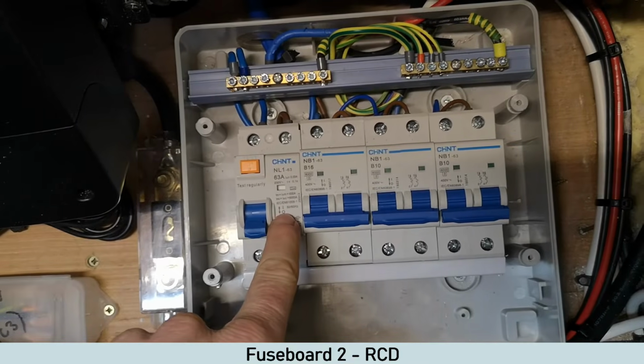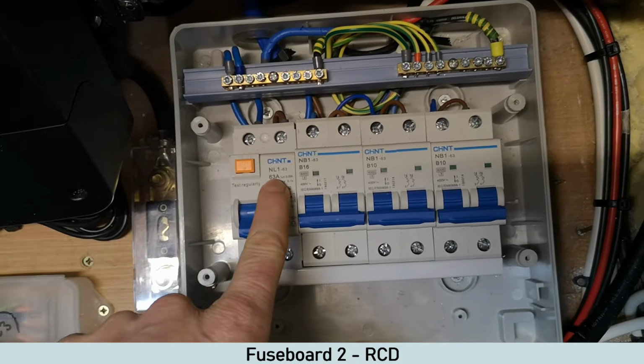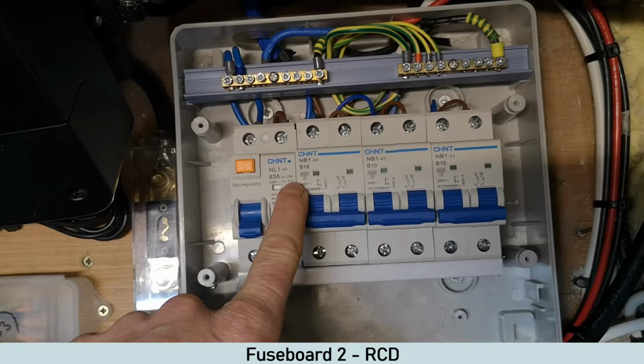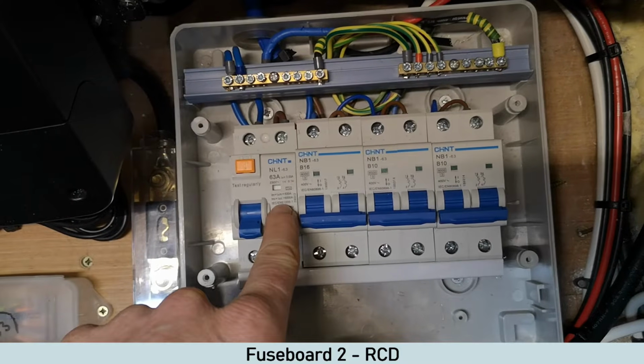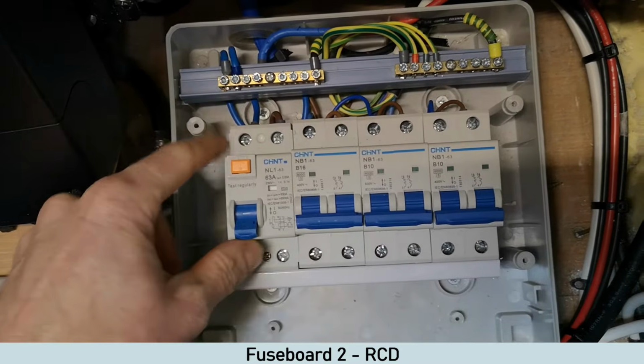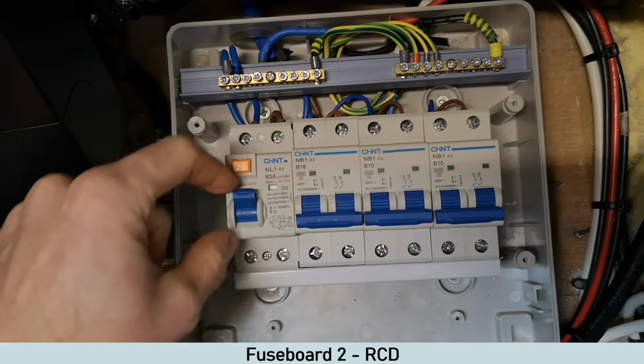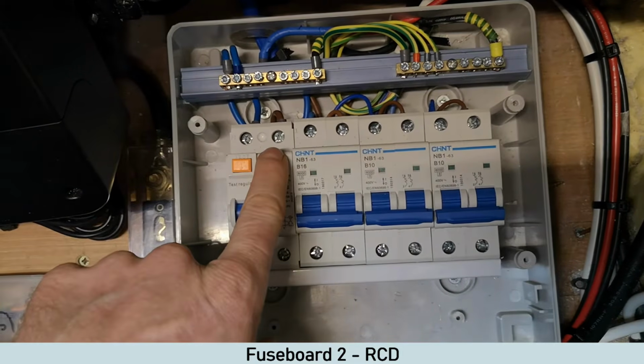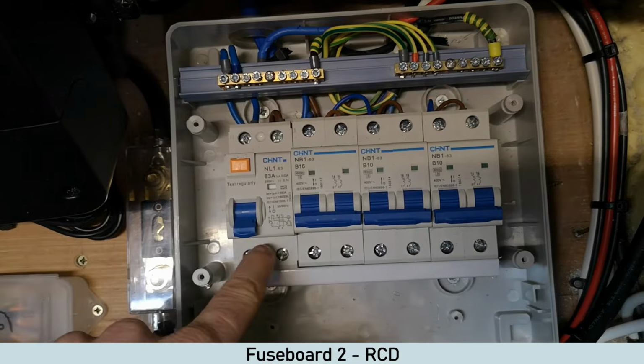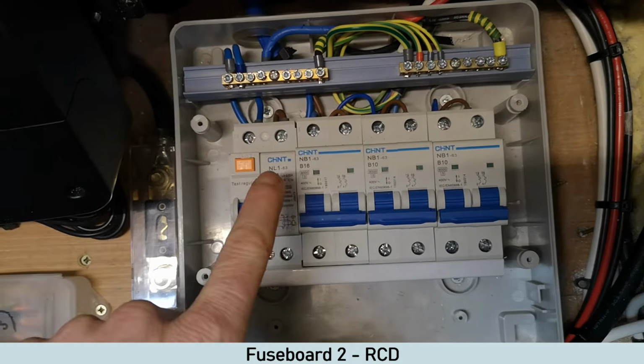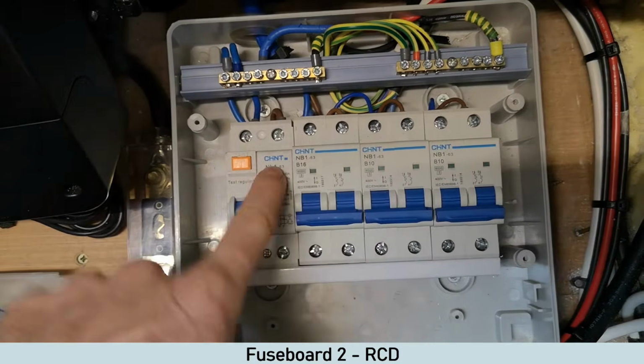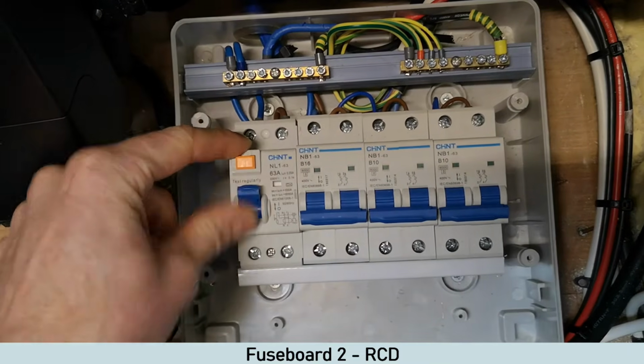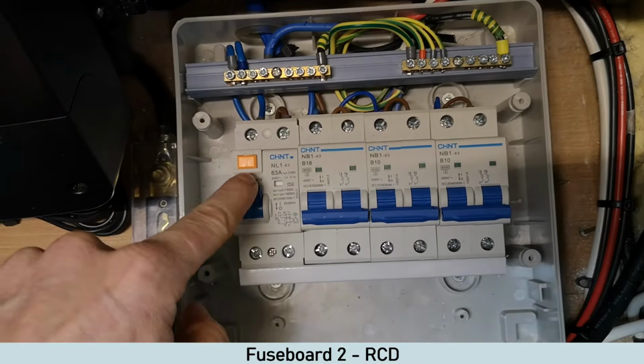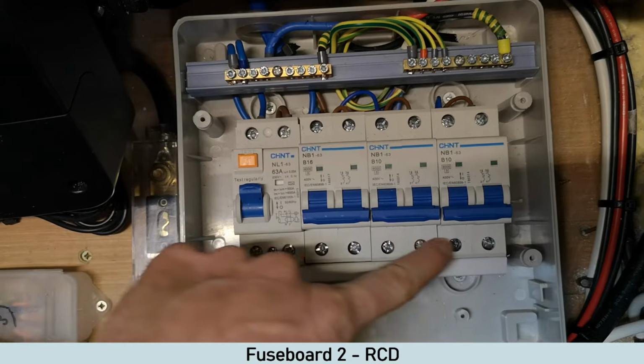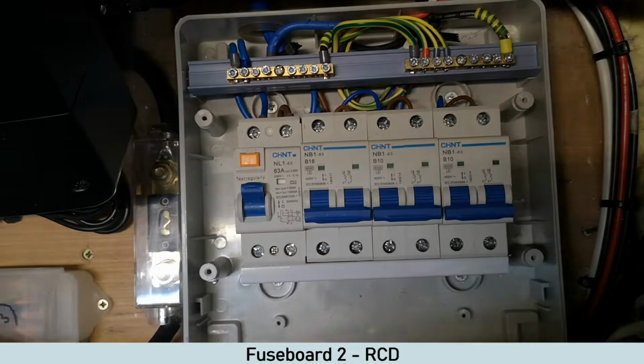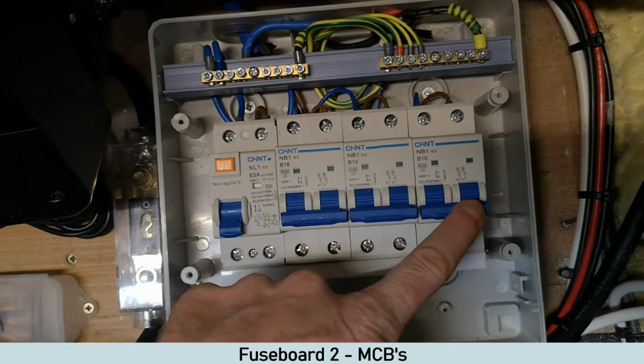So this RCD, the same applies for DB1. It's a 63 amp, 30 milliamp, because that's the max we can have, and it's a type A RCD. Also, it's double pole, so it isolates both live and neutral on the outgoing. So what will happen is the power from the inverter will come into here. Once that's switched on, we'll be able to press the test to check it works, and the power will then supply these circuits here.